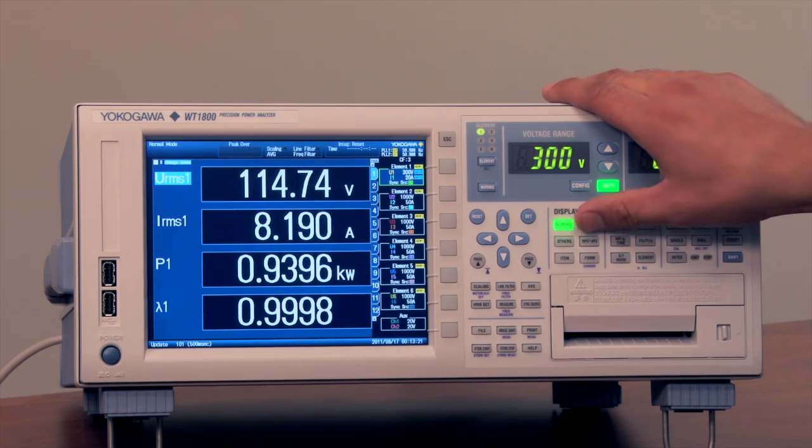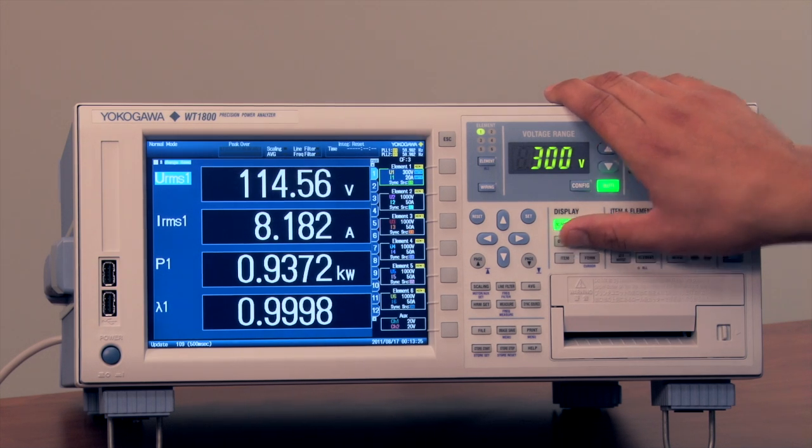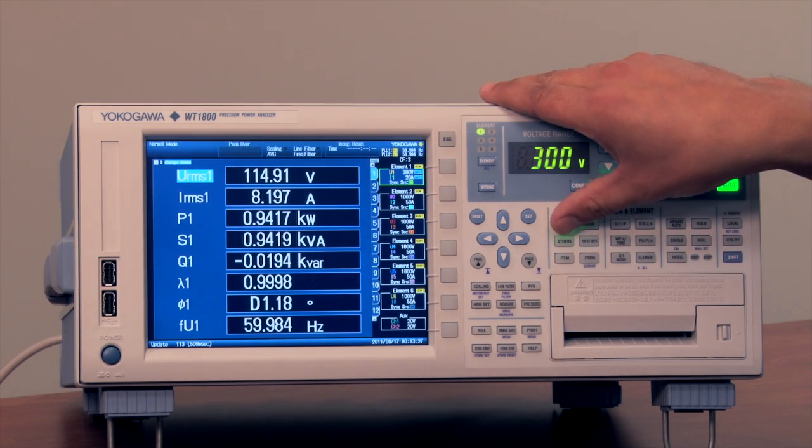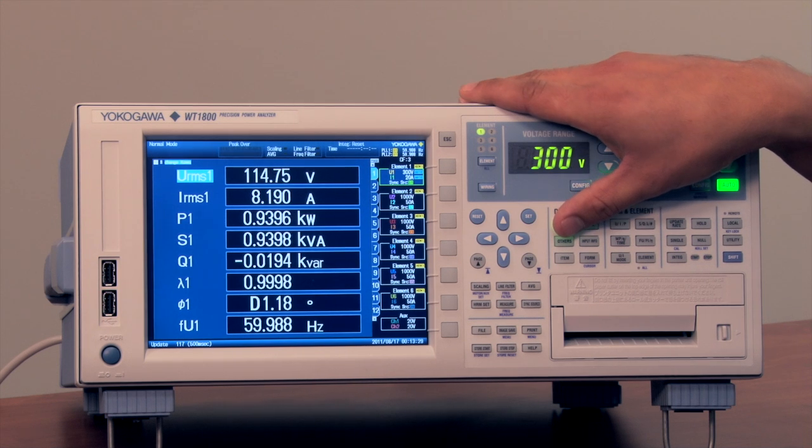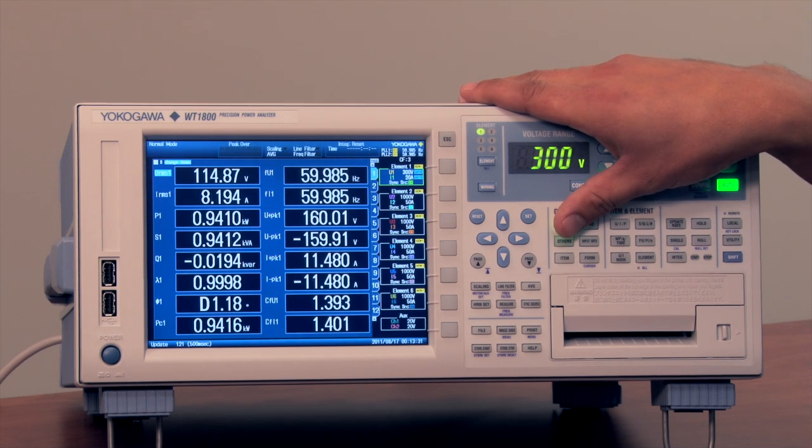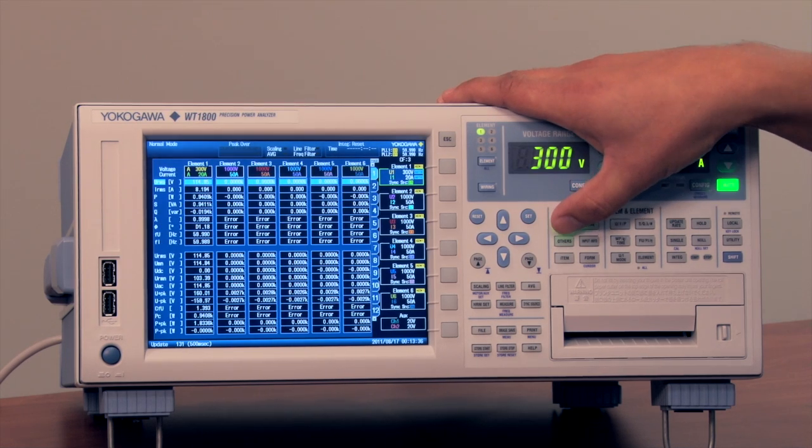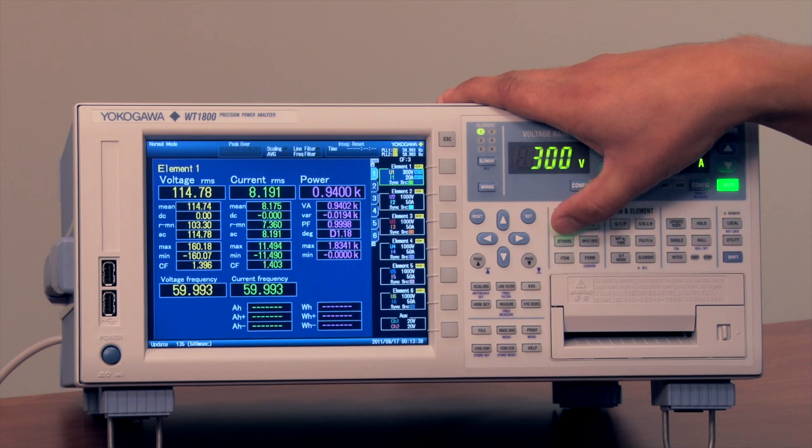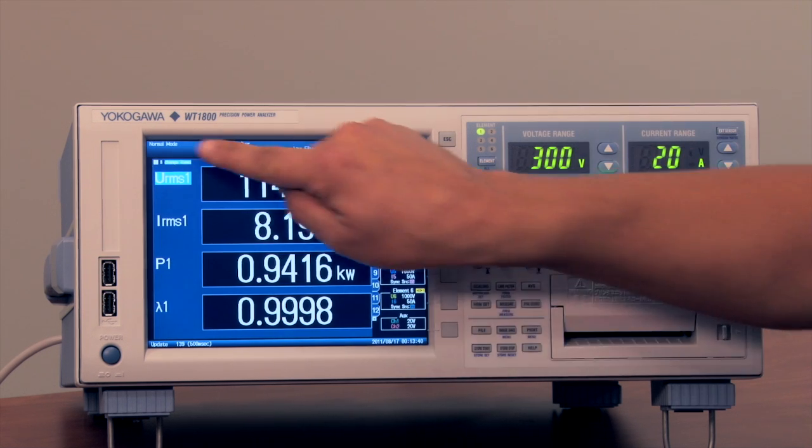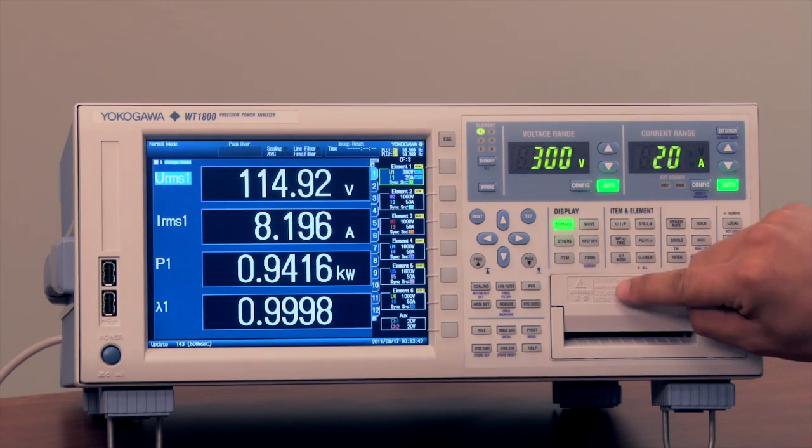You have the choice of looking at numeric values, waveforms, or a variety of different other features. As far as numeric values, you can change the number of values and for what elements you want to view measurements for just by simply hitting this numeric key and cycling through the various different displays. If you wanted to change any of these items you can easily use the quick set keys.